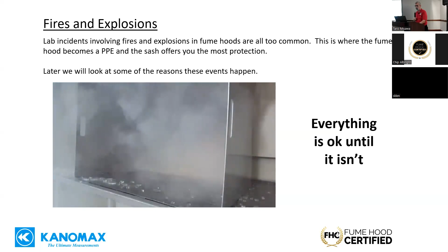So the problem with fume hoods is everything's okay until it isn't. You don't really know what's going wrong until it goes wrong sometimes. So you really want to train the user about safety. The sash is really a barrier between the user and what's going on in the hood. So if there's a fire or explosion, you really want that sash in front of you to shield you from what's happening in the hood.